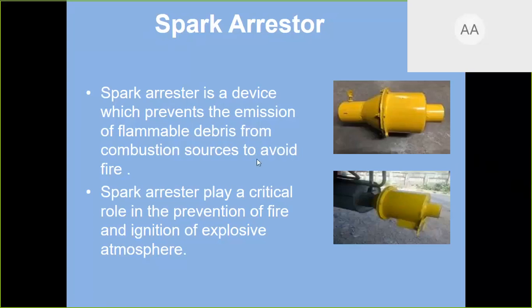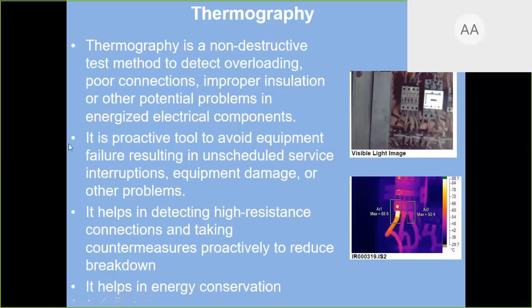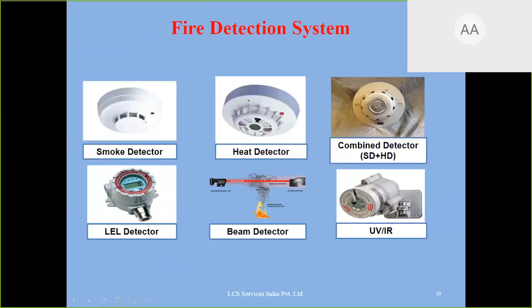And there's one more question from Mr. Sai Krishna. LEL is the lower explosive limit for any gas. We can install it, right? LPG is heavier, so we install the detector about 1 to 2 feet above the ground, not at the top, for LPG.